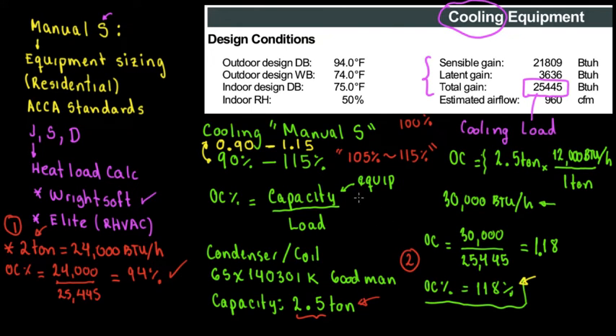All right so now one last thing. This manual, this part, see manual S says that you're going to be sizing from 90% to 115% but this is applicable for single speed compressor. Single speed compressor. Because sometimes you have two speed compressor which is multi speed, so in multi speed you can go up to 120%. Sometimes you have variable speed in that case you can go up to 130%. So that's the manual S.